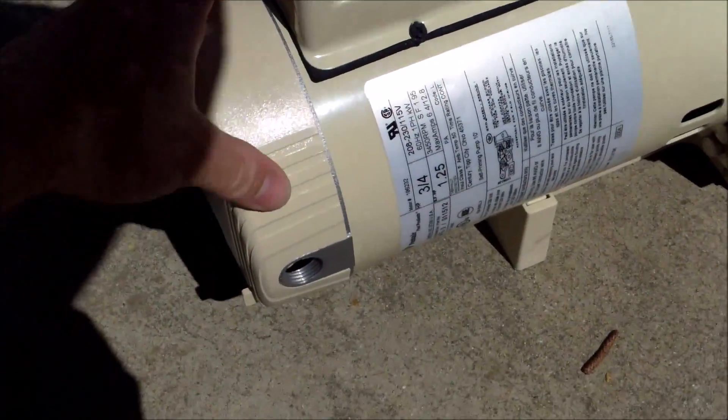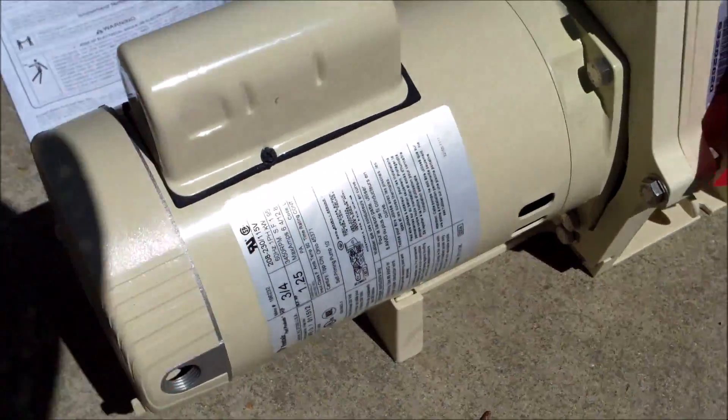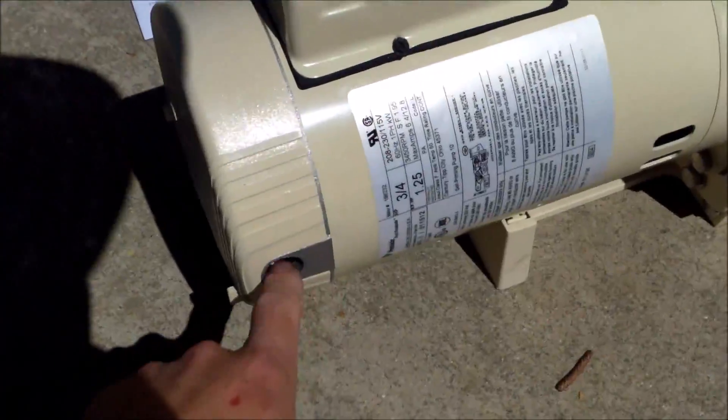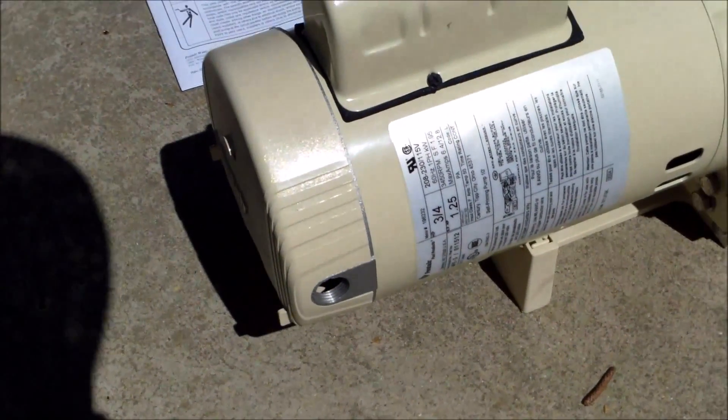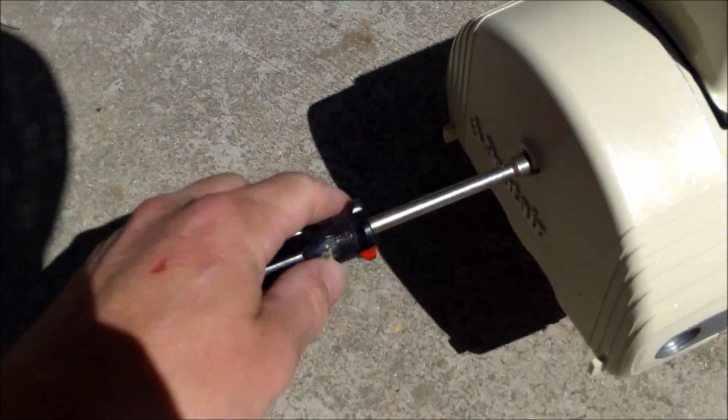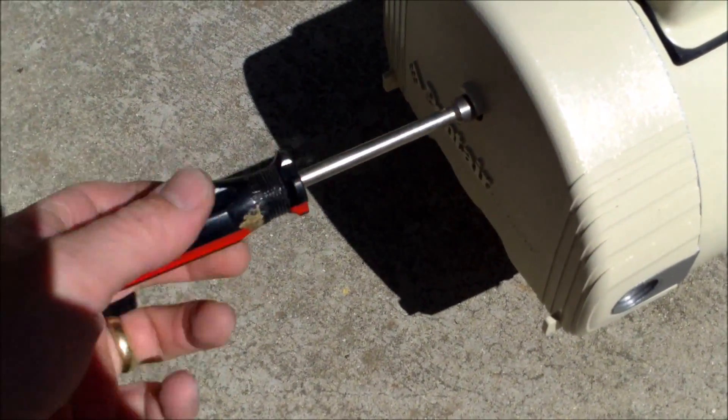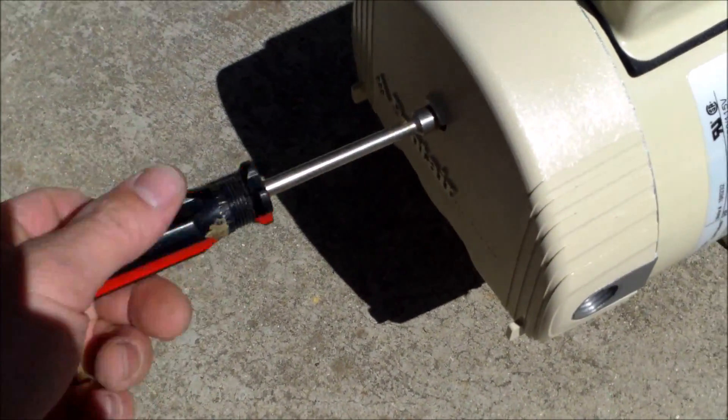In the first part I'm going to go over the wiring of the pump itself. All that comes in the box is actually the motor and the pump. You can use the existing wiring that comes out of the time clock if it's still in good shape. You need a 1/4 socket wrench to get the screw out the back of this particular pump model. Most of them are the same size, 1/4 screw to get to the wires.